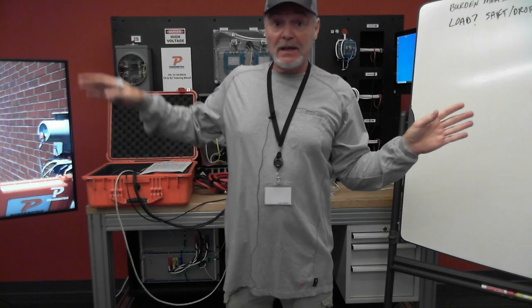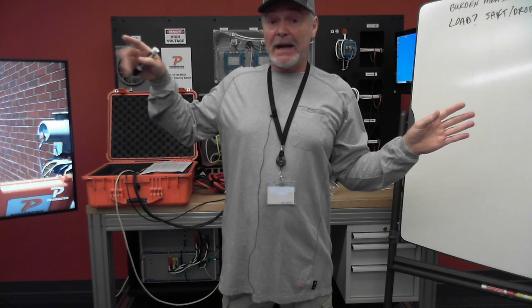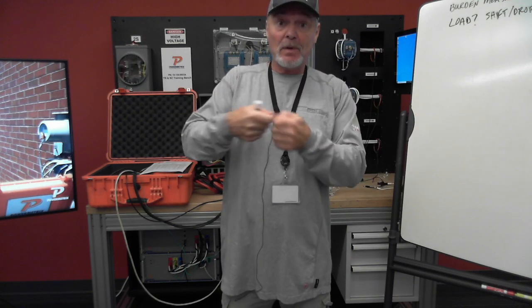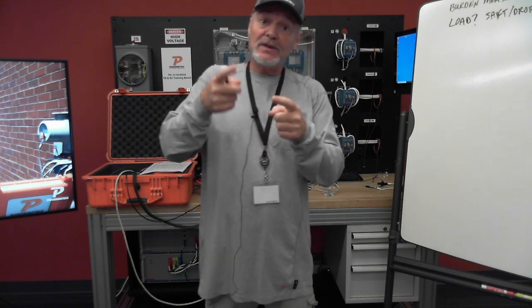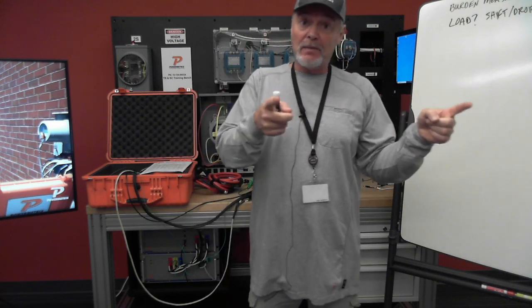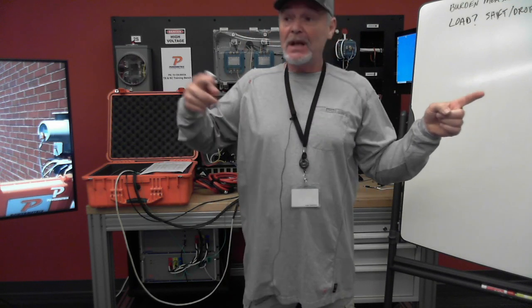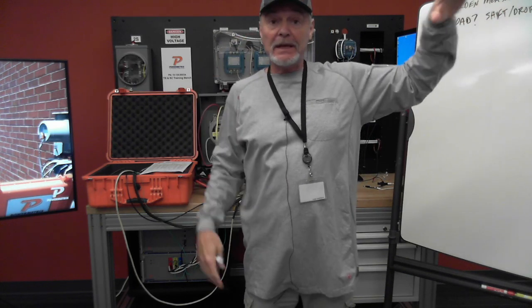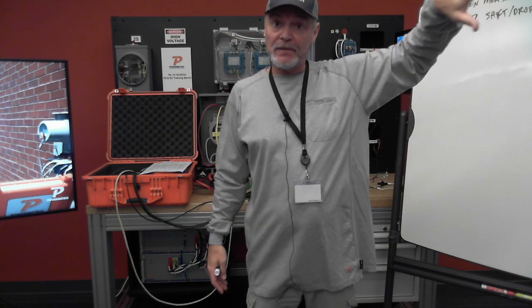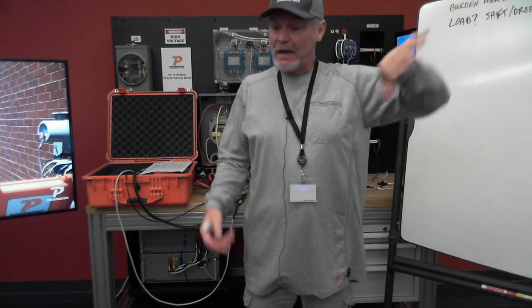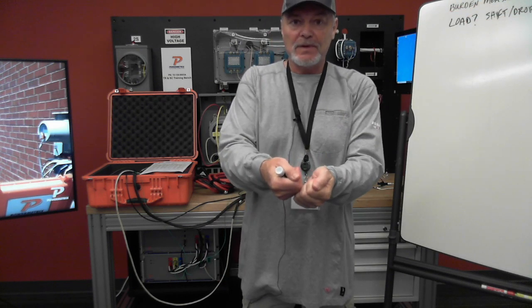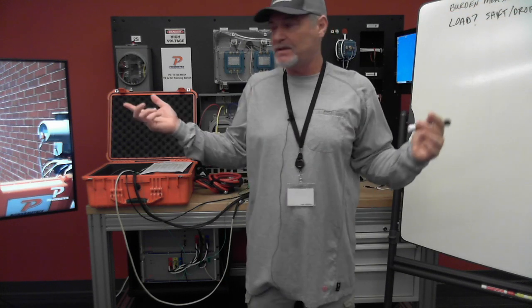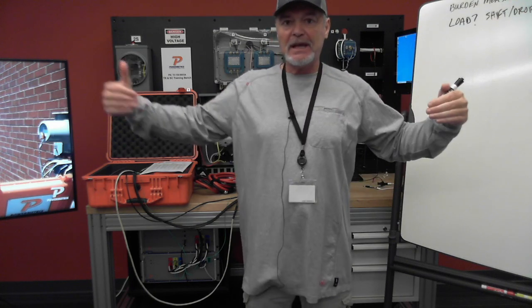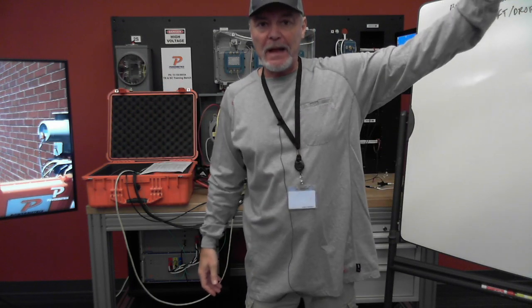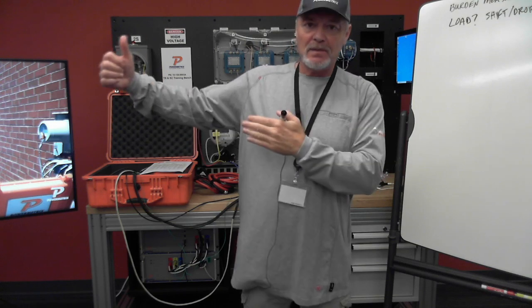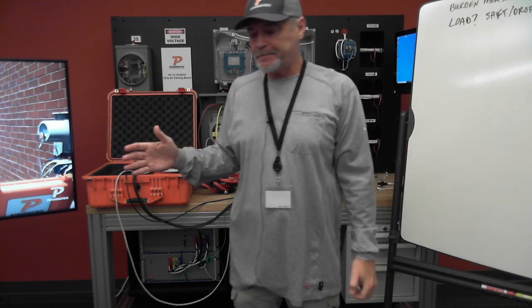Then we checked the extension, right, that I had. So we took the extension, made sure it wasn't my extension cable. Then we made sure it wasn't my standard probe adapter cable that connected to the extension. So you're just going down through, because you're getting an unusual reading coming off of the CTs, right? So we're not looking at alligator clips for the voltage at the test switch. This is a CT issue we're having here. So we're testing those connections, how we're reading from that primary for that CT all the way back to the machine. And we didn't see anything.